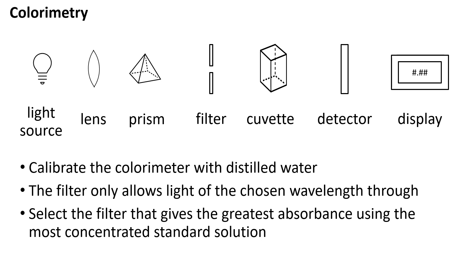The colourimeter must be calibrated to give an absorbance reading of zero when distilled water is in the cuvette. The filter only allows light of a certain wavelength to pass through. The filter that you choose depends on the colour of the solution that you are analysing. Select the filter that gives the greatest absorbance value with the most concentrated solution that you are testing. Double check that distilled water gives an absorbance of zero at this wavelength.